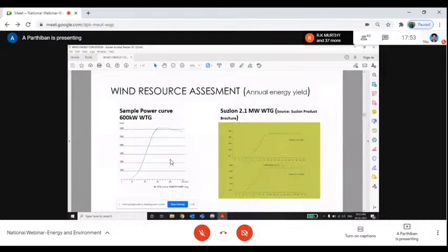For example, this 2.1 S97, at 3.5 meter per second, it will start power generation. At 11 meter per second, it will reach 2.1 megawatt. Up to 20 meter per second; once the wind speed reaches 20 meter per second, the wind turbine will stop. But generally in the southern area of India, it will not go beyond 18 or so. It will go up to 20, but after 20 it will not go. Some wind gust may be there for a few minutes, like 5 minutes, but the maximum will be less than 20 meter per second, in the southern part of India.